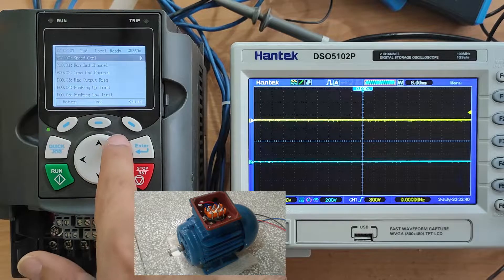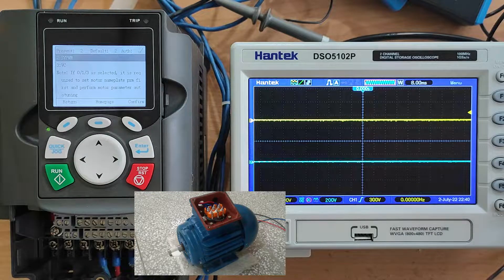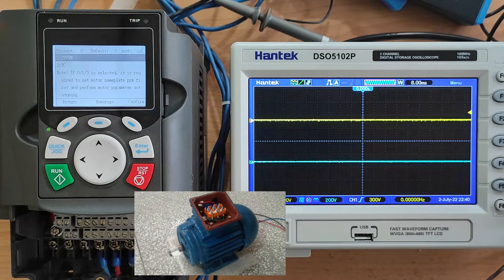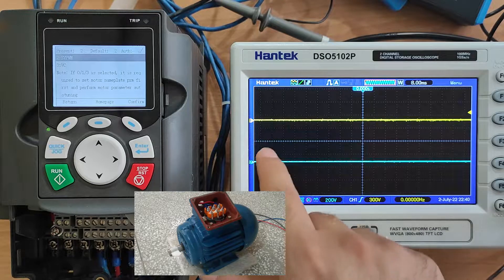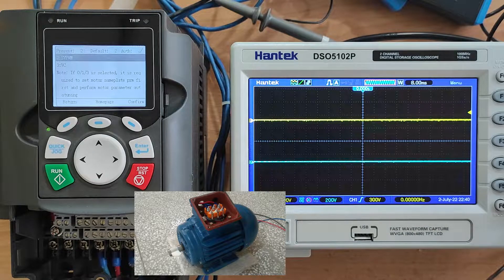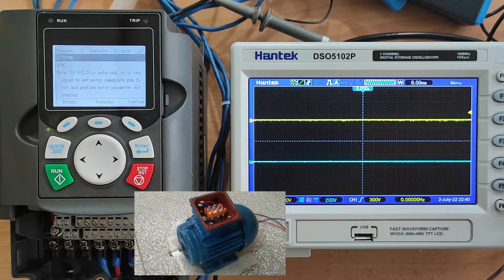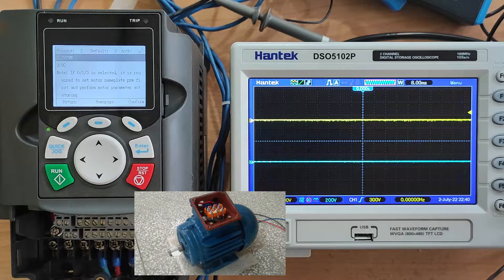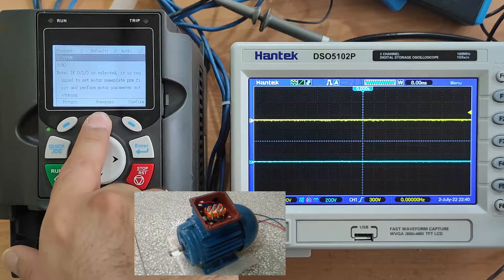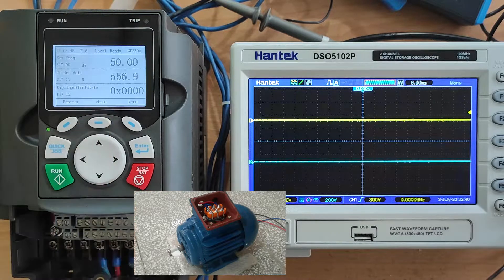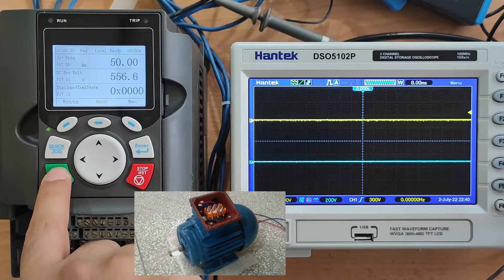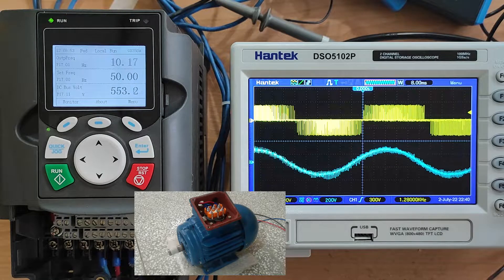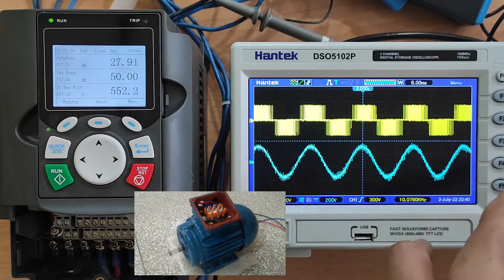Speed control, SVPWM. I want to show you what the waveform of the line-to-line voltage and line current look like during start and stop. So let's go back to the home page and run the motor. Channel one shows the line-to-line voltage waveform, and channel two shows the line current.